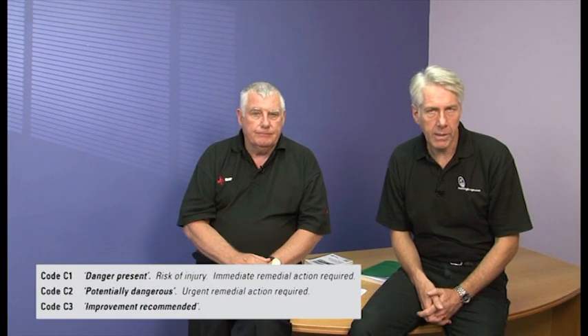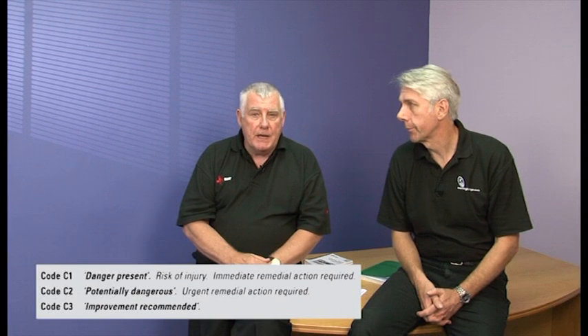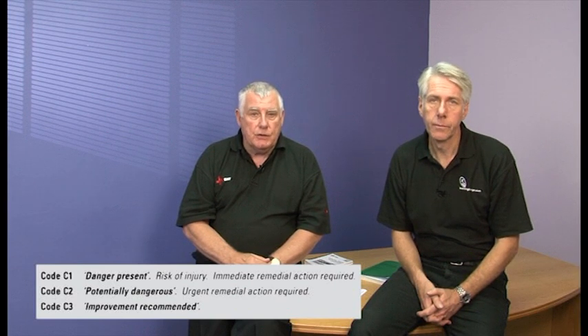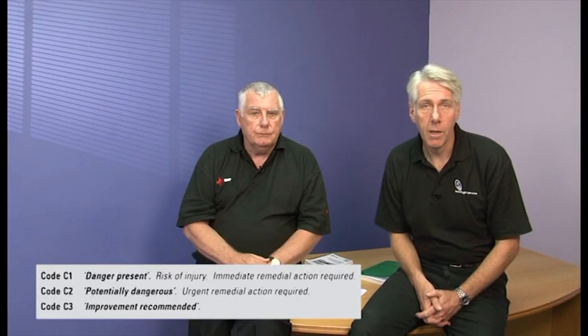There are 3 observation codes used to determine the degree of urgency for action. These are C1, C2 and C3. C1 means danger present and immediate remedial action is required. C2 means potentially dangerous and urgent remedial action is required. Code C3 means improvement recommended. When it comes to making the overall assessment of the condition of the installation, any C1 or C2 conditions that have been identified must result in an unsatisfactory outcome.